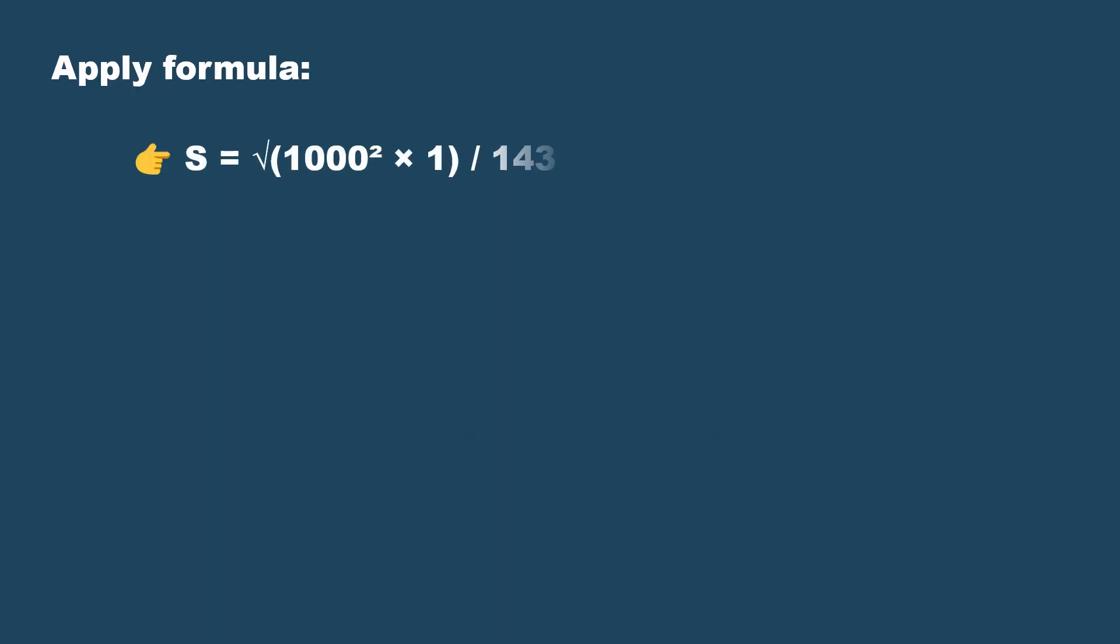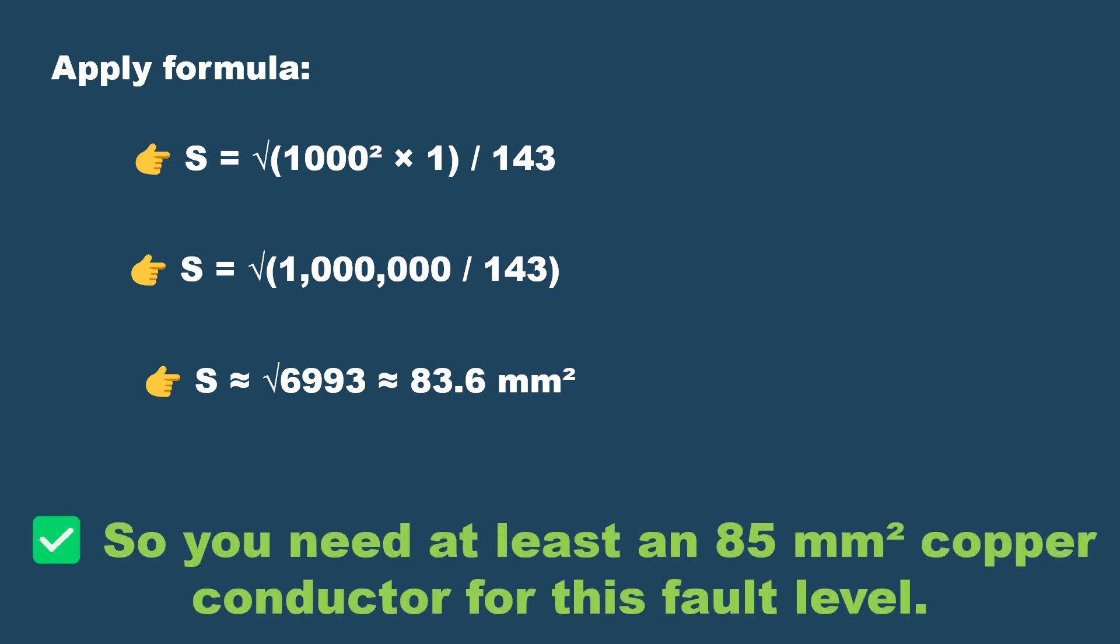Put the values in formula: S = √(1000² × 1) / 143. So S = 83.6 mm². You need at least an 85 mm² copper conductor for this fault level.